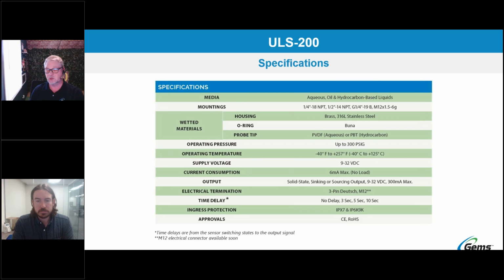The operating temperature, wide temperature range. We want this for outdoor applications. So we have it from -40 up to +257 Fahrenheit, which is 125 Celsius. Supply voltage to operate the sensor is 9 to 32 volt DC. Anywhere in that range will power the device. The current consumption, very low at 6 milliamp, that's without load. The output is solid state. That means no moving parts. It's all electronics. We already mentioned that it's got the sinking or sourcing output, the voltage range, and it has a 300 milliamp max output.